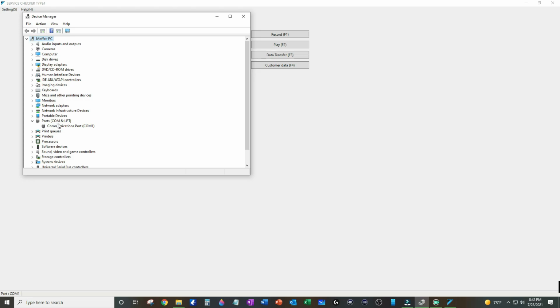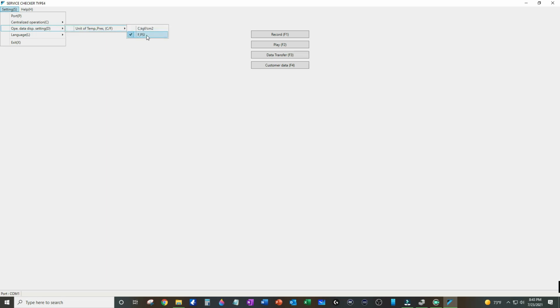We're also going to select permission in the central operations setting, which will allow us to control the indoor units from our computer while recording. We'll talk more about this shortly. Last, make sure to select the proper unit of measure. I'm going to be using Fahrenheit and PSI in my area. Once we've set up the parameters, click on Record.